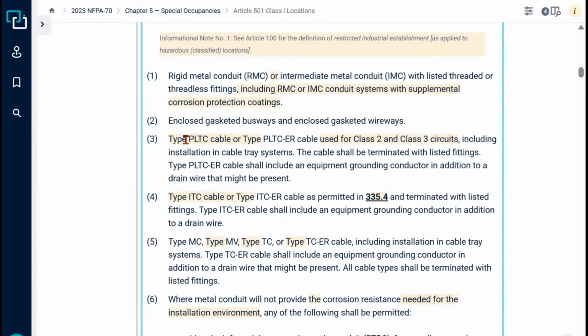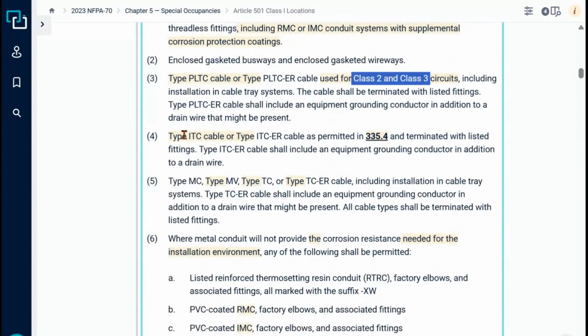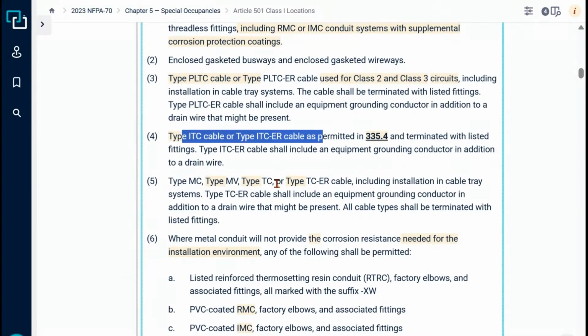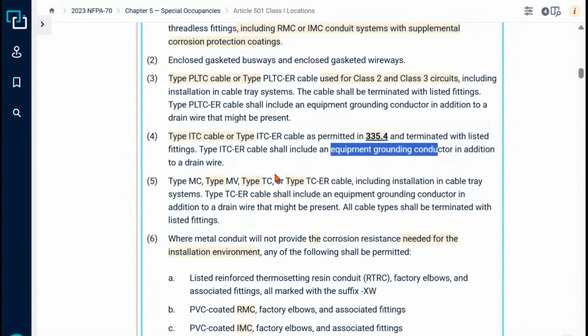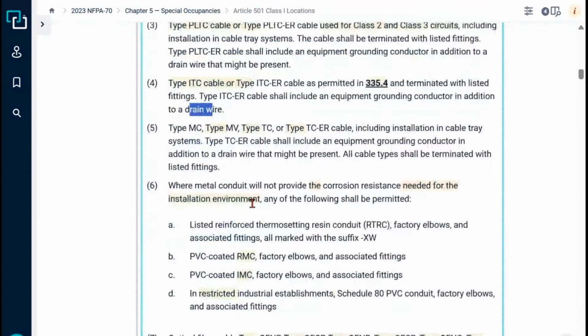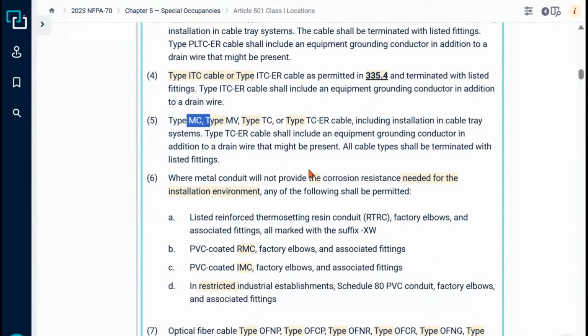Here you've got PLTC, okay? Power limited tray cable applications. This is typically for Class 2, Class 3 applications. You get a little allowance there. ITC, instrumentation tray cable, you get a little bit of allowance here. Less stringent, okay? It has to include an equipment ground, but less stringent, and it has to have a drain wire. MC, interesting, because this isn't hazardous location MC. This is just regular MC. So you get some relaxation in Division 2 that you don't get in Division 1.